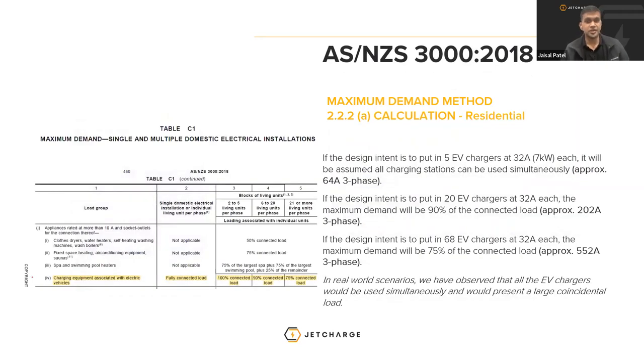When it comes to residential installations, typically if you wanted to connect 2 to 5 living units per phase, which is essentially a 7-kilowatt charger connected for one of the apartments, you can have up to 15 chargers on 3 phases, and you would have to consider 100% of the load of that EV charger. For example, if the design intent is to put in 20 EV chargers at 32 amps each, the maximum demand would be 100% of the 90% of the connected load, approximately 202 amps, 3-phase.